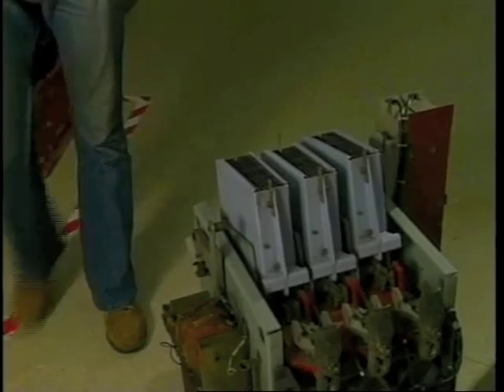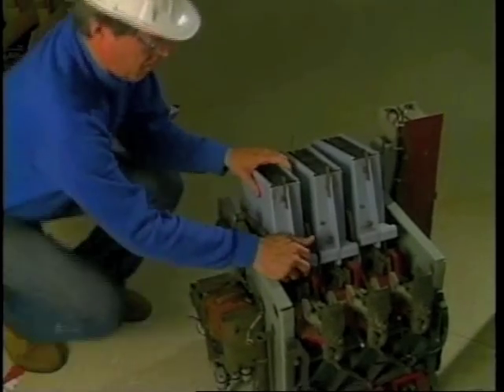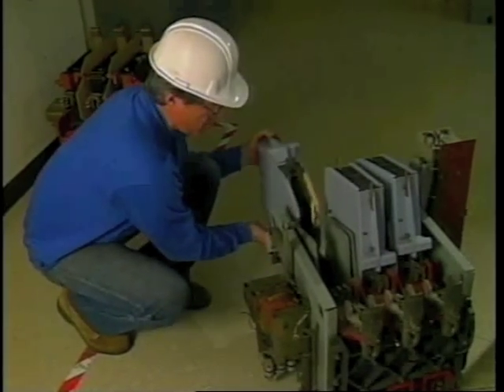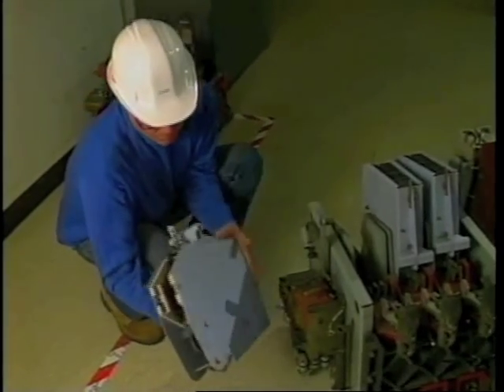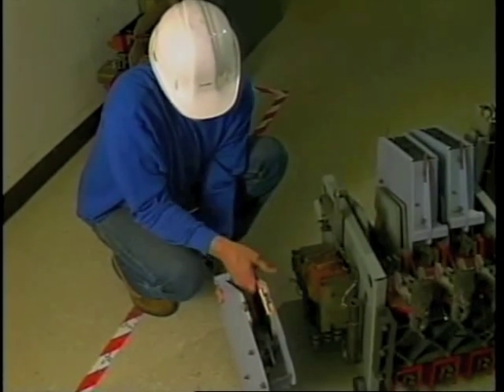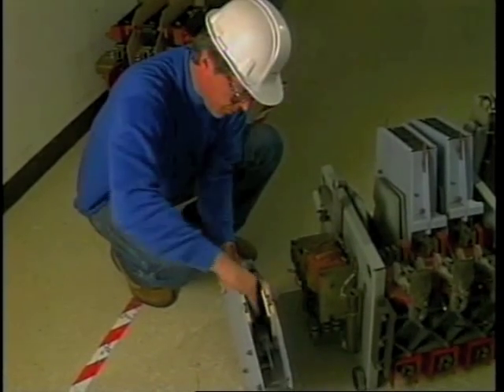All contactors have arc chutes that interrupt arcs during fault conditions. The arc chutes on contactors are smaller than those found on circuit breakers and should be visually checked following each fault condition and during routine maintenance. This should be performed while the contactor is de-energized and isolated from all control and backfeed power sources.